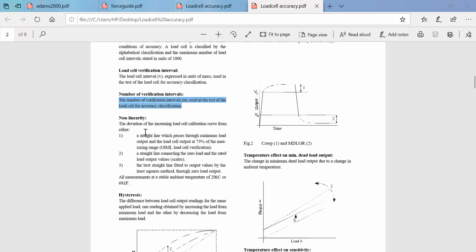if it is non-linear or not. So the first constraint is a straight line which passes through the minimum load output and the load cell output at 75% of the measuring range. Okay. So what do you understand from this? If it is varying linearly, the actual and the measured values match without much error, so that is a linear version. If it has to be non-linear, what is one of the criteria? A straight line passing through the measurement of the load should have deviations. How? Minimum load output. So for the minimum load, it should provide a load cell output of 75% of the measuring range. Then you will come across some variation. It is not varying linearly. It is coming into a non-linear aspect. So this is one of the criteria.